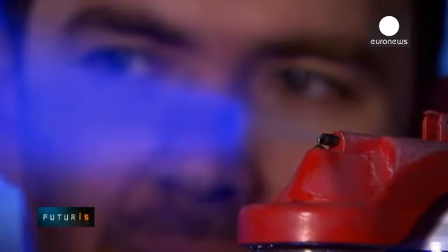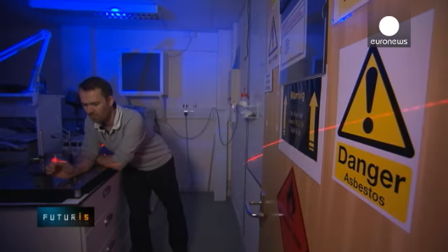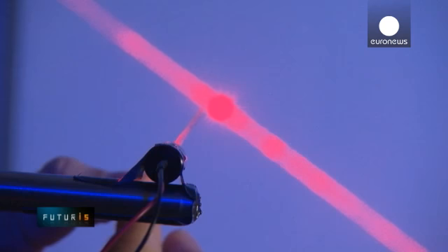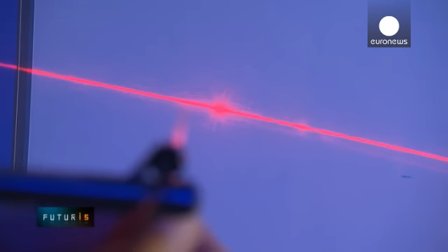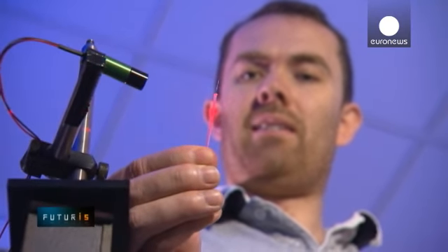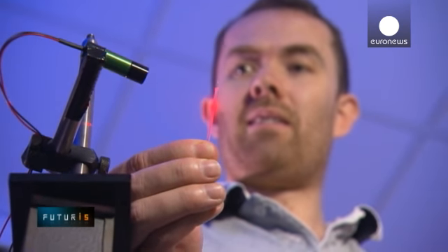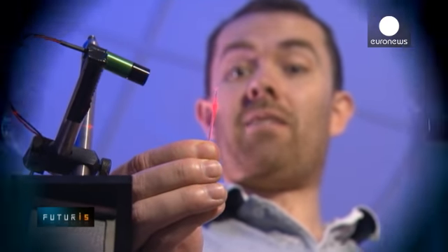When exposed to magnetic fields, asbestos fibres react in a very particular way. They rotate. Researchers match that property with laser science to develop their device. This fibre is about 1,000 times larger than an asbestos fibre, but when we introduce it to a laser beam, it illuminates in exactly the same way as an asbestos fibre would, creating a very, very similar scattering pattern.